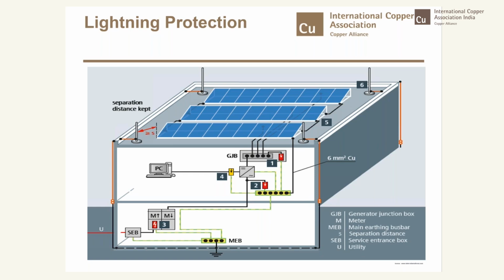On the rooftop, you have the lightning air termination rods, where the number and height of the rods depend on the LPS required for that zone. Depending on the lightning protection zone, lightning protection system classes are defined. Based on that, you can estimate the number of earthing conductors, using either the rolling sphere method or the inclination angle method. Either can give you the coverage area of the air termination rod, to what extent that rod will protect the modules from direct lightning strikes.